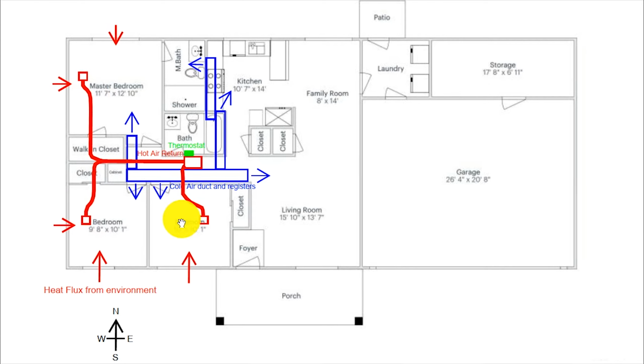They make a regular duct, which has less pressure drop, and flexi duct in larger sizes, which I could have gone with, but I went with the 6-inch flexi because I figured these are pretty short runs, and the higher pressure drop of flexible duct of this middle size probably wouldn't be a big issue. To address possible system imbalances, I installed louvered butterfly valve couplings where each of the 3 flexi ducts connects to the main return.